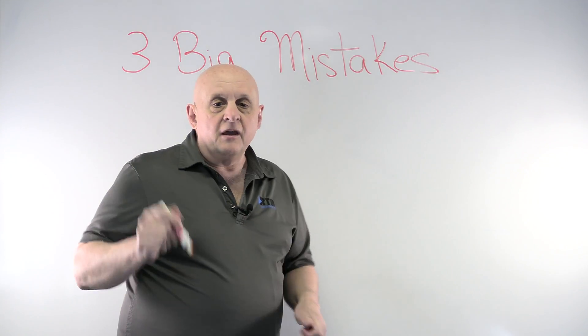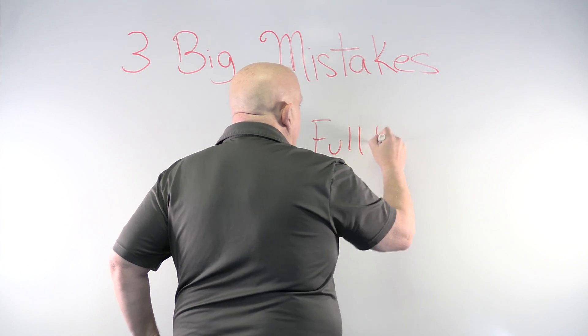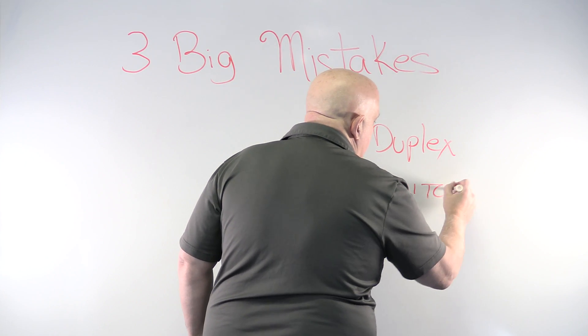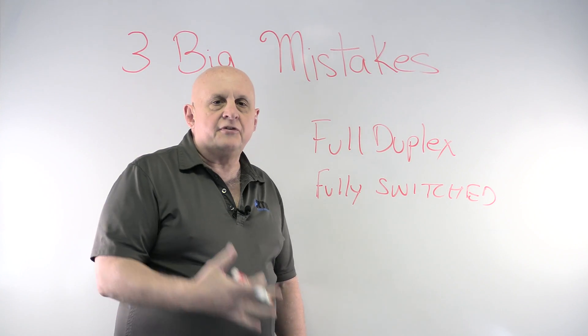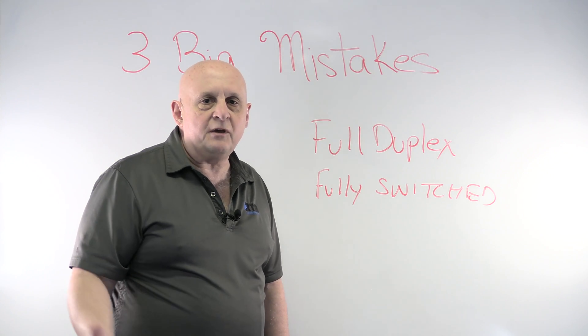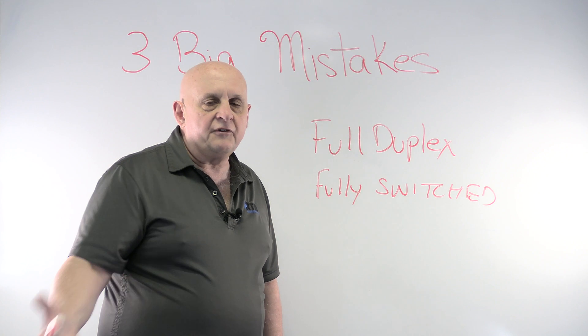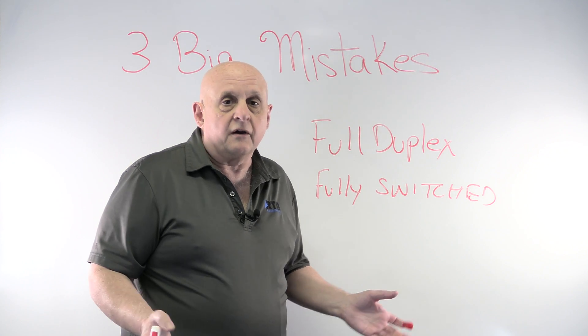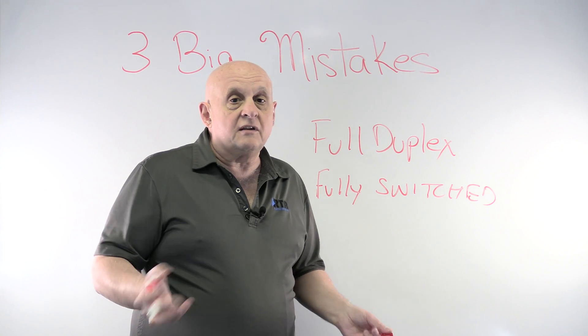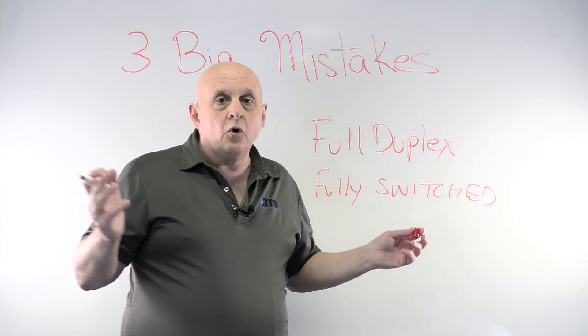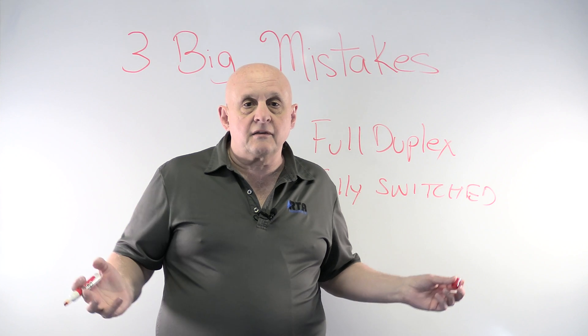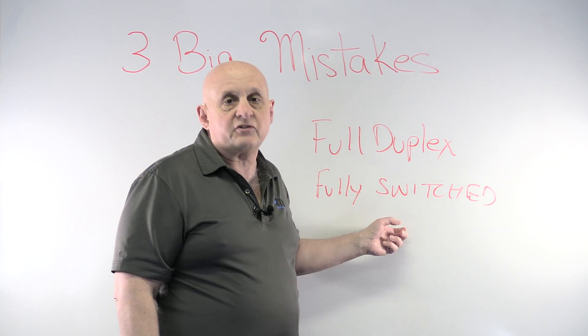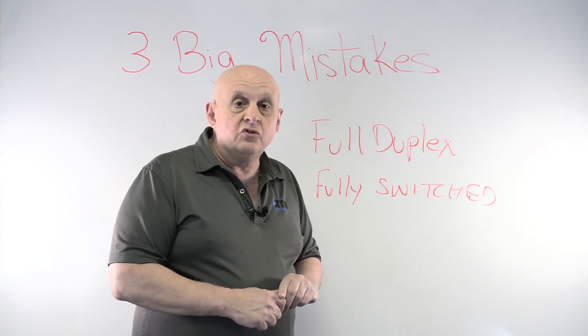The first mistake that people make is not using full duplex on a fully switched network. People are still using things other than switches — some are trying to use hubs, some other kinds of physical layers. The EtherNet/IP and CIP specifications don't say much about the physical layer, so you can make these mistakes. You need to use a fully switched network, meaning switches — I prefer managed switches — and you have to make sure all your devices are using full duplex.